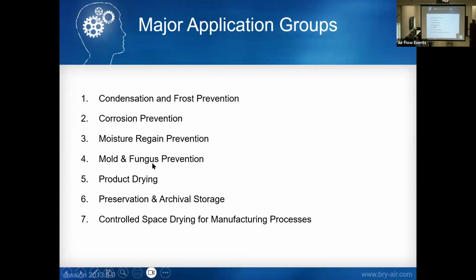I just have one, and it's a general one. For a long time, I honestly didn't understand a lot about dehumidification using the solid wheel. Now that I've sat through a number of presentations, it seems like controlling the wheel itself to get rid of moisture is a fairly simple and predictable process, and the difference between manufacturers of desiccant systems is really on the application know-how side. Is that fair? Yeah, the application know-how. Maybe your wheel's a little deeper, but remember, in the industry there are really two depths of rotors: a 200 millimeter and a 400 millimeter depth. Those are about the only two industry depths. As far as diameters, they also affect performance a little bit.